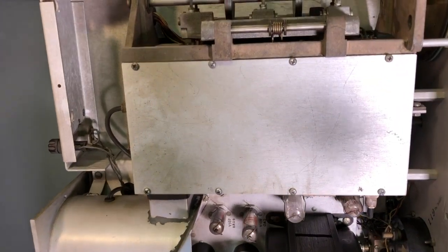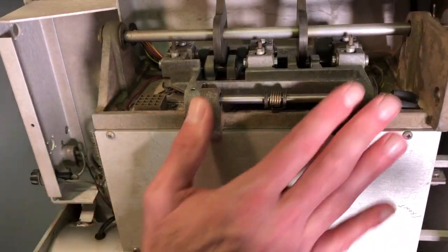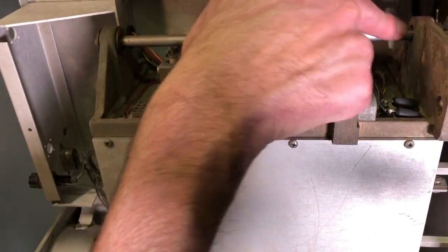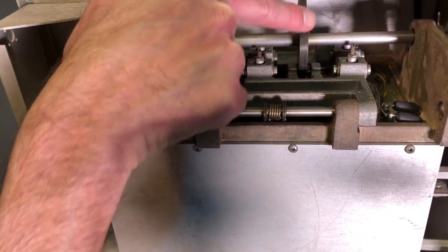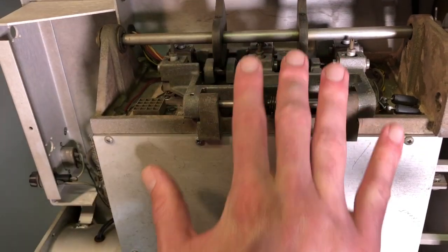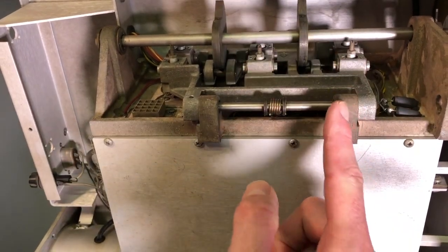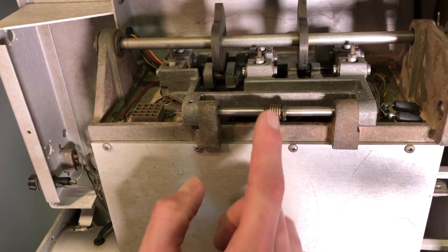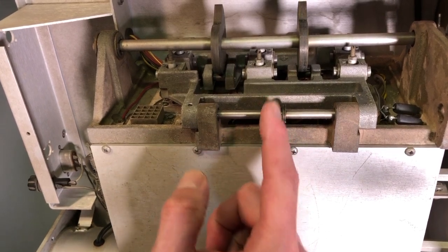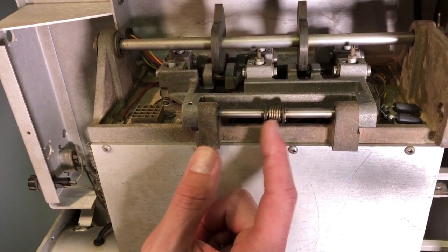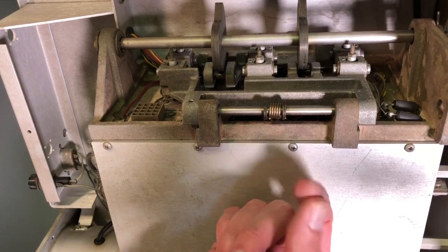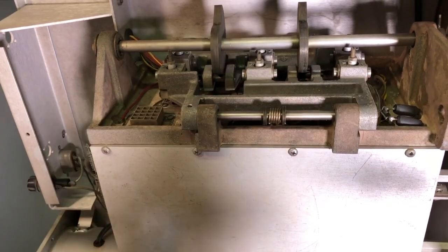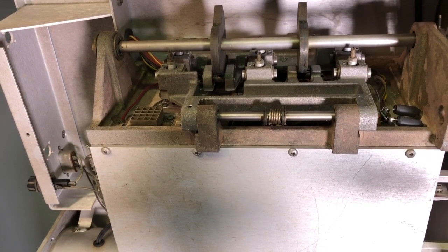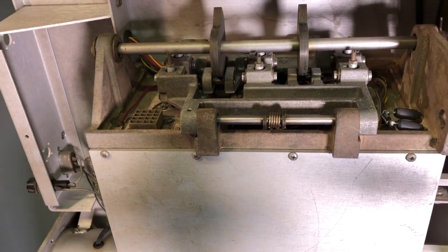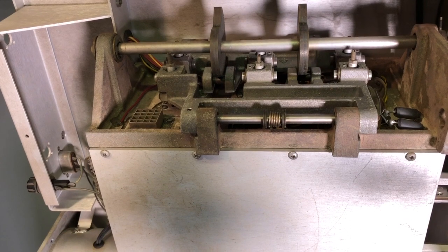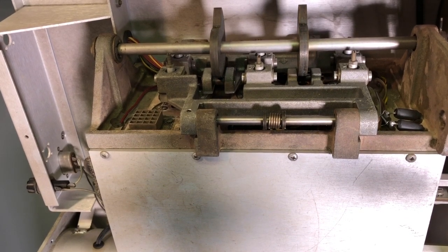If I tip this all the way up here, you can see this mechanism in here for the tuning. This shaft rotates. These cams, as they rotate, cause this mechanism to press inward. It pivots across here, and you can see there's a spring right here. In fact, this spring has old dried grease. It's almost sticky, sort of viscous, but with a sticky feel to it. I'm sure that's down in numerous areas on the pivots and things like that, these bearings back here. So those need to be cleaned up, and that'll probably free right up again.